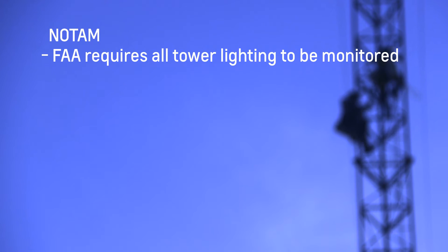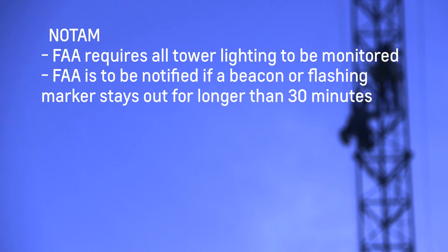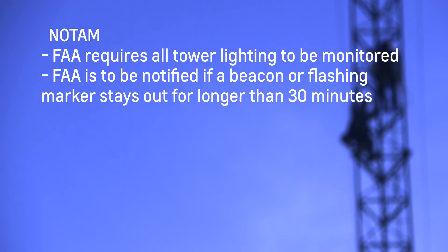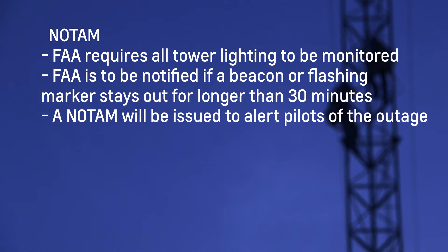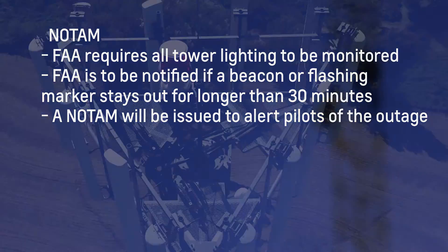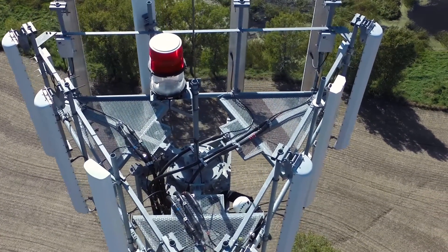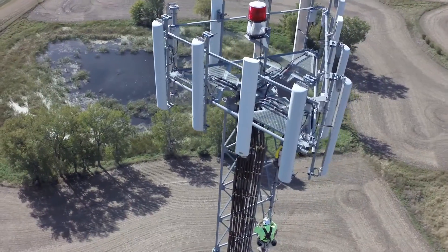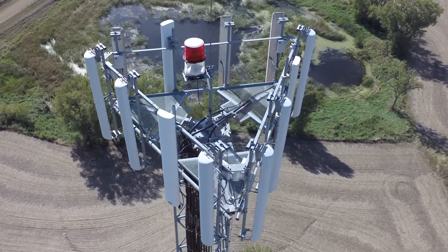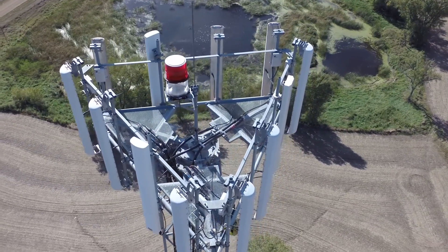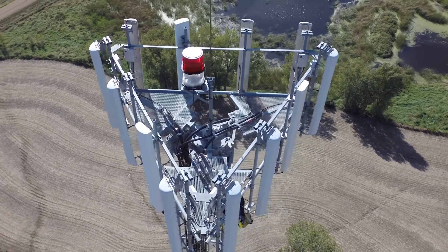Monitoring - Notice to Airmen. The Federal Aviation Administration requires all tower lighting to be monitored. The FAA is to be notified if a white beacon, red beacon, or red flashing marker stays out for longer than 30 minutes. A Notice to Airmen will be issued to alert pilots of the outage. An extension must be filed if the lighting repair cannot be completed within the time frame provided. The FAA should be notified to close the open NOTAM when repairs are completed. Failure to notify the FAA in the specified time will result in the NOTAM being automatically closed.